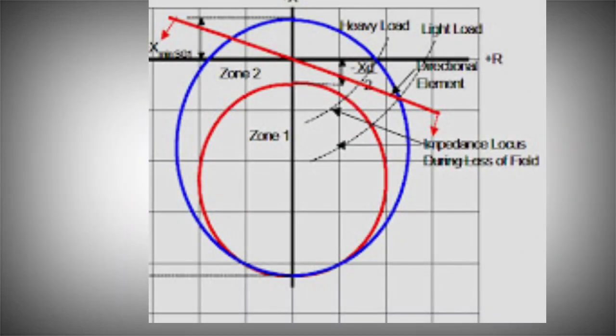Now, looking at the graph: the generator has an under-excitation limit with Zone 1 and Zone 2. Zone 1 and Zone 2 are defined based on impedance. When under-excitation is detected, Zone 1 is the inner region. If the positive sequence impedance value is low and the under-excitation fault condition is reached, Zone 1 is entered. Under-excitation Zone 1 triggers a trip command with 0 seconds delay.